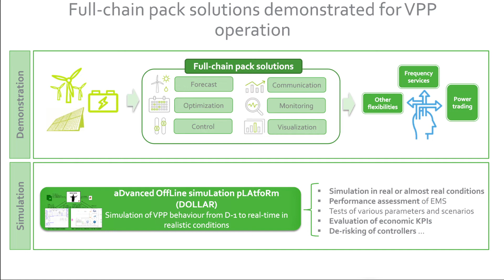More concretely, the EMS of the VPP comprises 2 layers. The operational planning scheduler provides optimal energy and multi-service schedules for the VPP every 30 minutes at most, based on the most recent forecasts and measurements available, and the short-term control, which is designed to manage the deviations and unexpected events within each scheduling time step, and sends more detailed set points every 5 seconds to each resource.